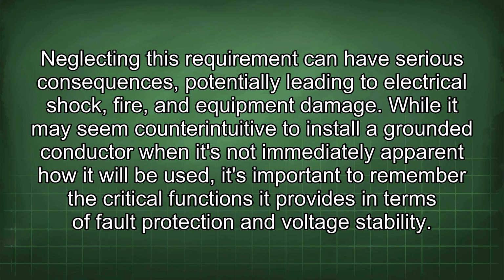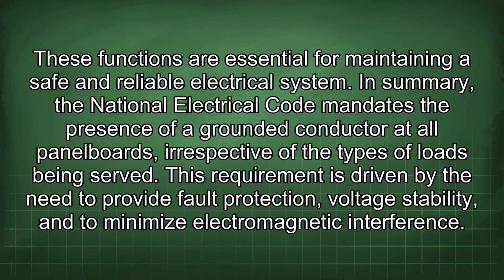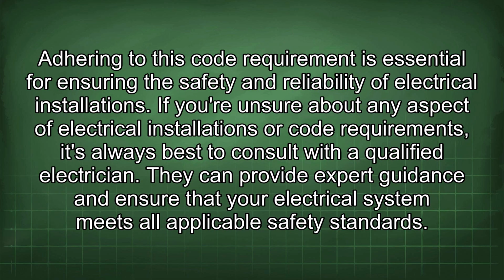While it may seem counterintuitive to install a grounded conductor when it's not immediately apparent how it will be used, it's important to remember the critical functions it provides in terms of fault protection and voltage stability. These functions are essential for maintaining a safe and reliable electrical system. In summary, the National Electrical Code mandates the presence of a grounded conductor at all panel boards, irrespective of the types of loads being served. This requirement is driven by the need to provide fault protection, voltage stability, and to minimize electromagnetic interference. Adhering to this code requirement is essential for ensuring the safety and reliability of electrical installations.